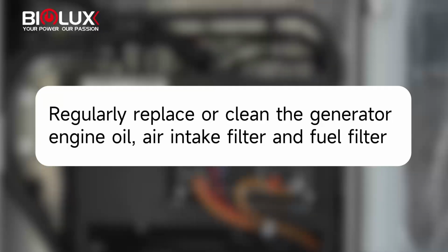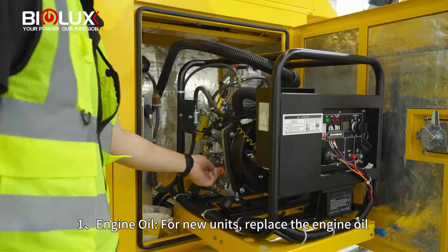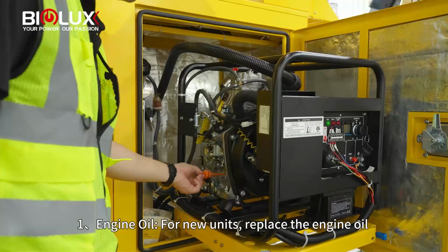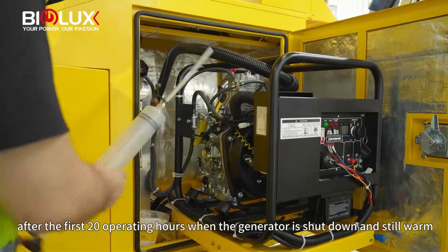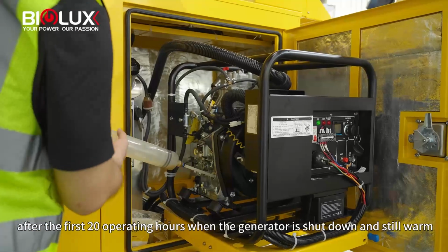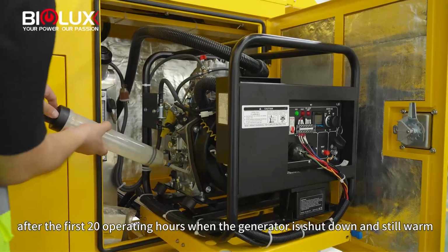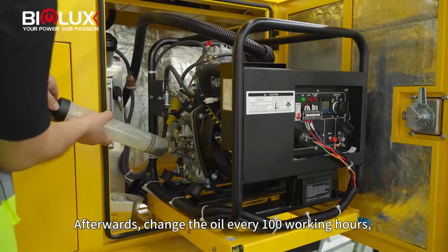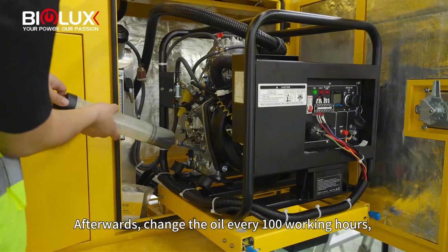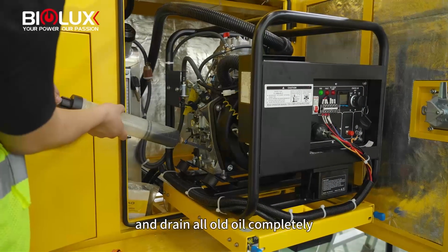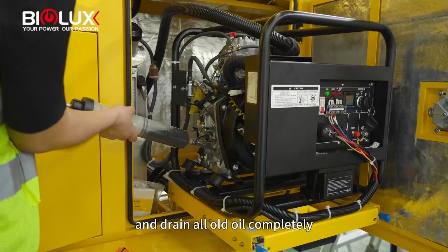Regularly replace or clean the generator engine oil, air intake filter and fuel filter. 1. Engine oil. For new units, replace the engine oil after the first 20 operating hours when the generator is shut down and still warm. Afterwards, change the oil every 100 working hours and drain all old oil completely.